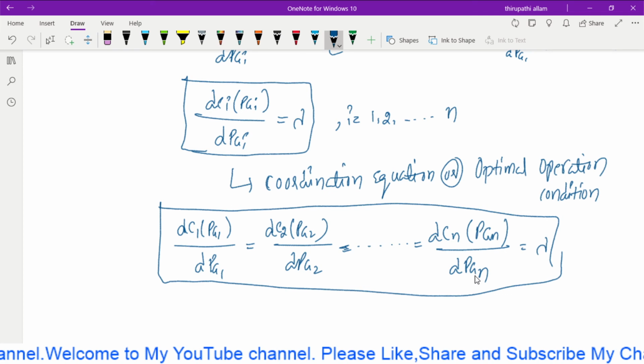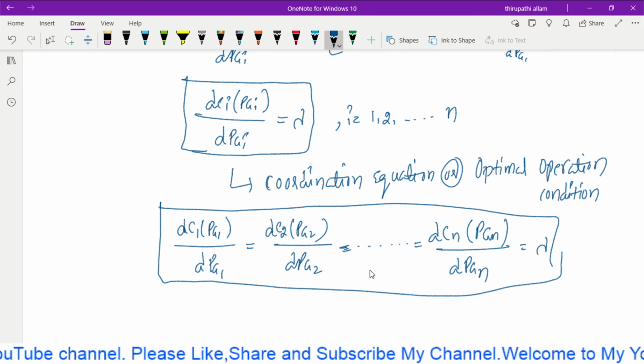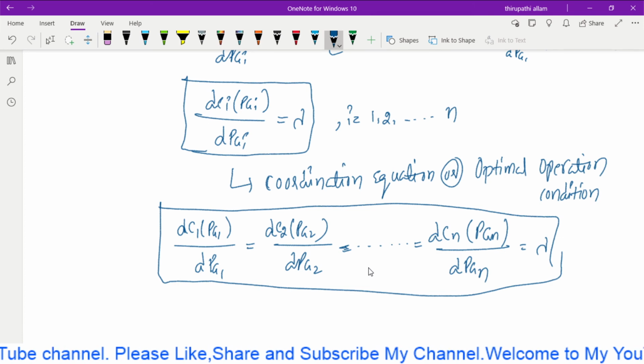Now this is what we can call the incremental fuel cost. The incremental fuel cost of all the plants is to be the same. This is nothing but the optimal loading condition. The optimal loading of generators corresponds to the equal incremental cost point of all the generators. So finally, this is the coordination equation or optimal operation. Here lambda is nothing but the Lagrange multiplier, equal to the fuel cost equation.